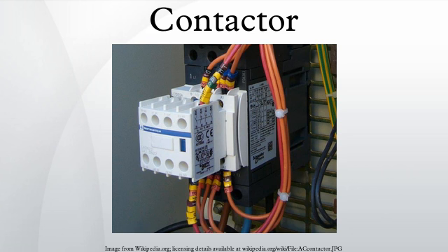The first to make contact and last to break will experience the greatest contact wear and will form a high-resistance connection that would cause excessive heating inside the contactor. However, in doing so, it will protect the primary contact from arcing, so a low contact resistance will be established a millisecond later. Another technique for improving the life of contactors is contact wipe.